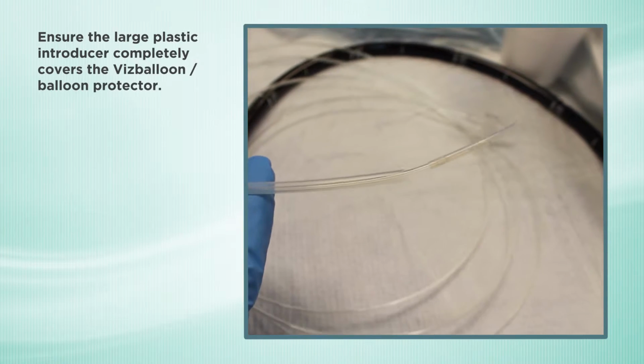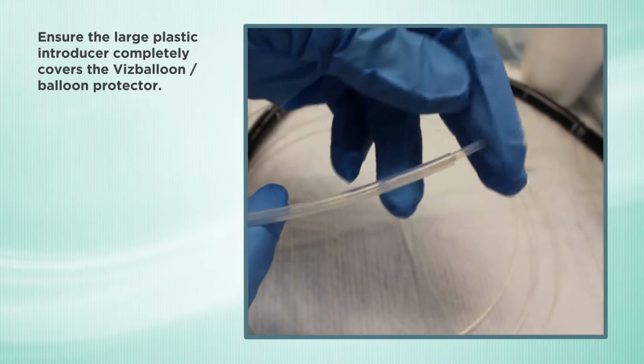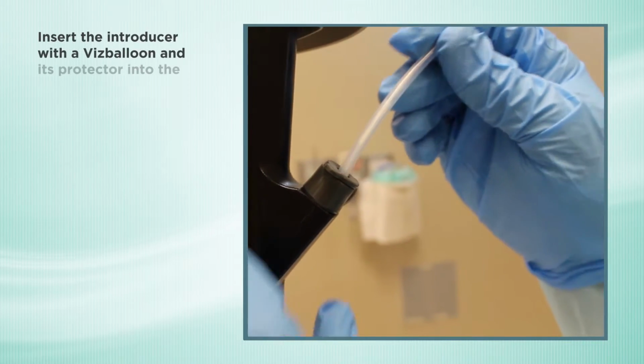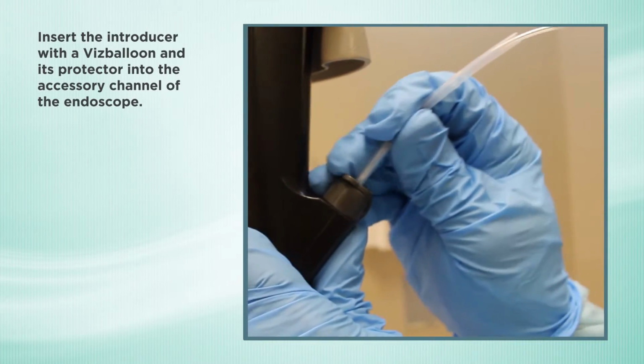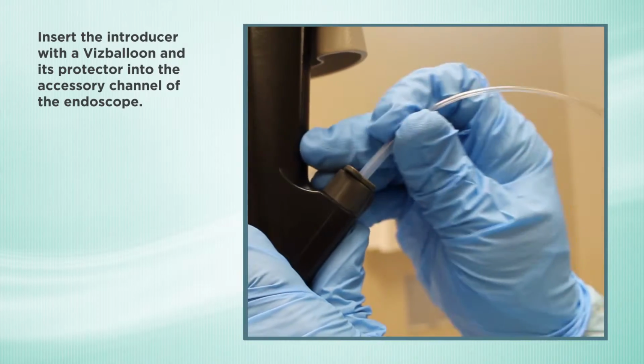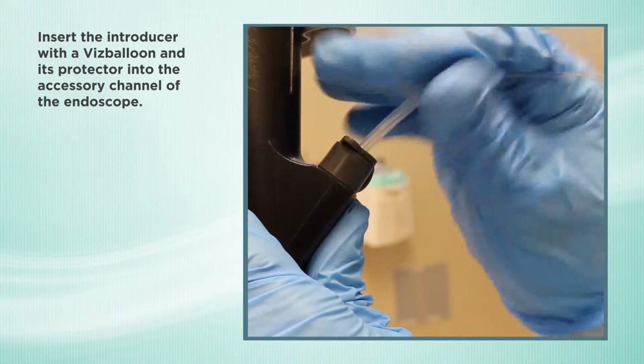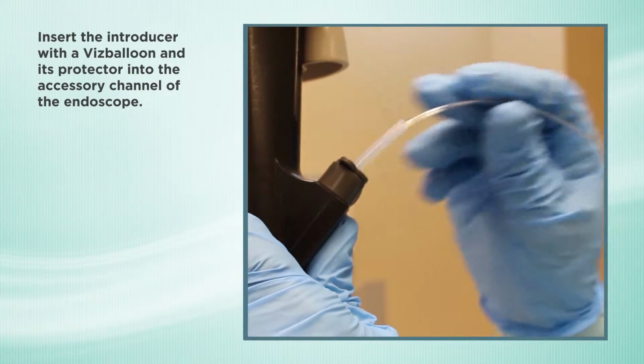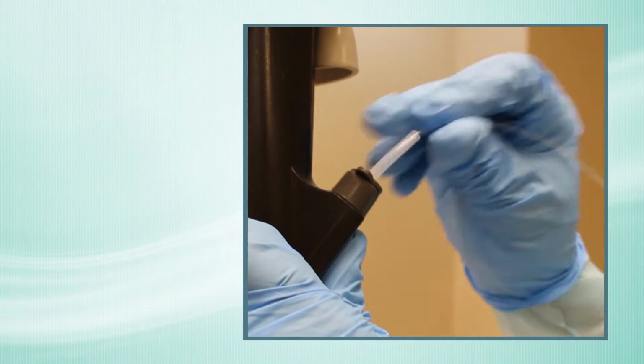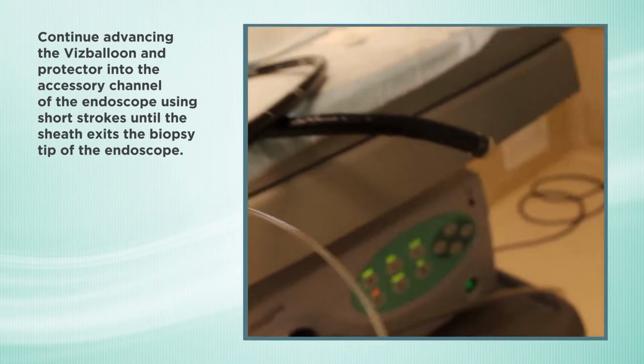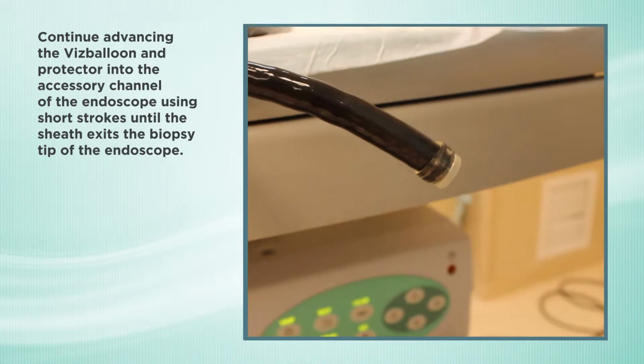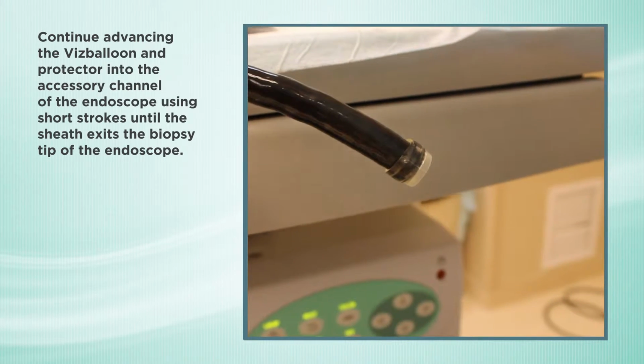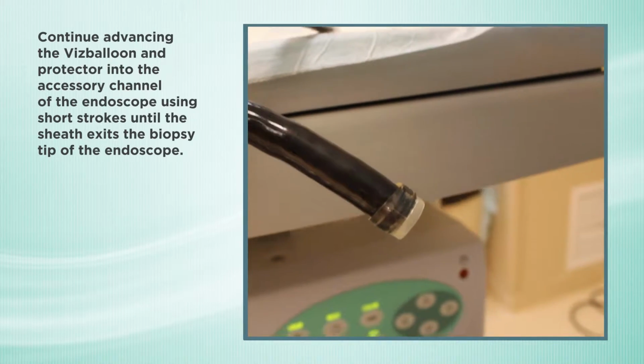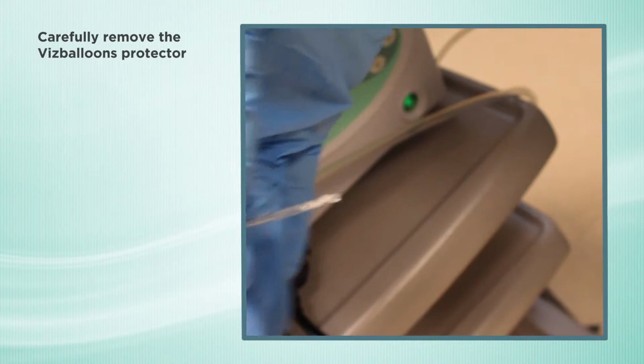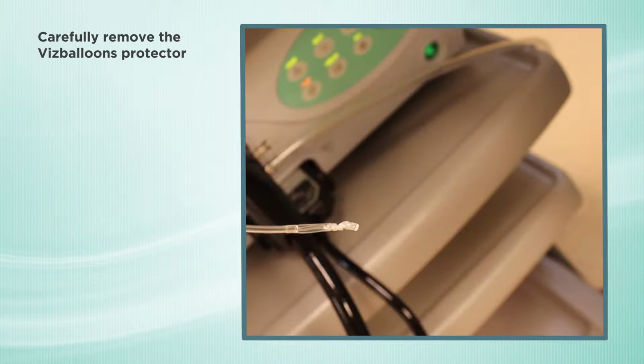Ensure the large plastic introducer completely covers the Vizballoon balloon protector. Insert the introducer with a Vizballoon and its protector into the accessory channel of the endoscope. Continue advancing the Vizballoon and protector into the accessory channel of the endoscope, using short strokes until the sheath exits the biopsy tip of the endoscope. Carefully remove the Vizballoon's protector.